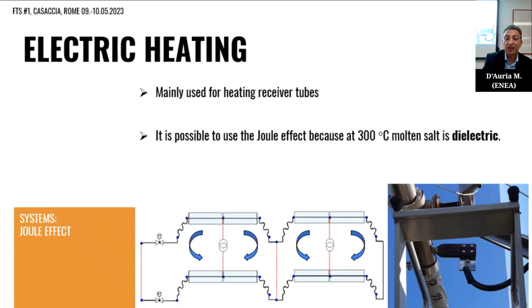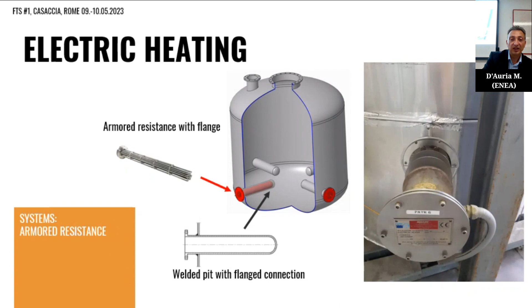So for heating a vessel, a tank, and so on, it is possible to use armored resistance, but it cannot be in contact with molten salt because it has a flange connection. A flange connection should be avoided because of possible leakage of molten salt from the plant. So it is better to have a welded pit, such as this, to which to connect the armored resistance. We have a picture of a practical installation.